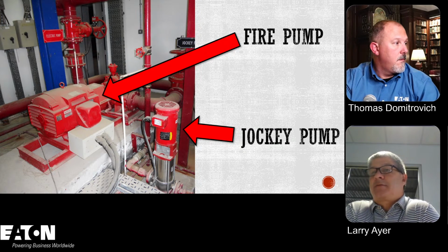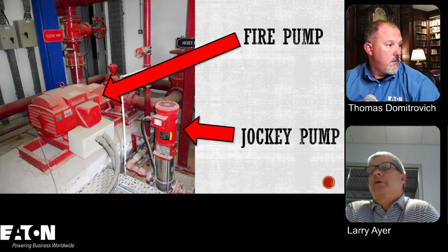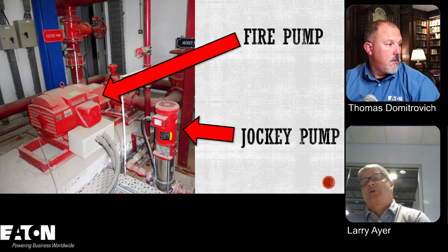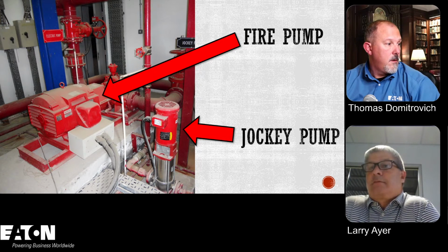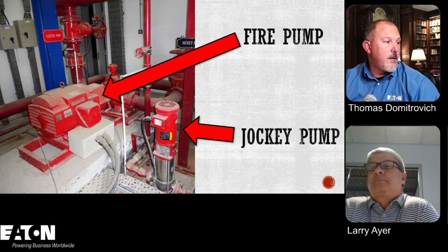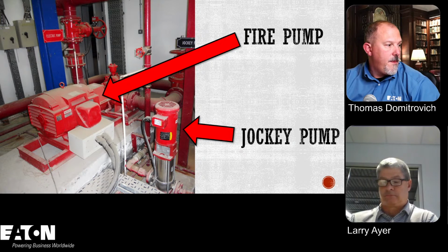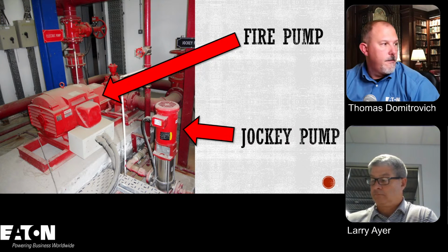I know that they have to be listed, and they have to be a little sturdier than your standard motor, so it can withstand some severe conditions when it's trying to operate. Yeah, so I'm looking. It says the standard for fire pump motors is UL 1000 and hold on. Added here, Standard 1004. So there is a specific standard for fire pump motors, and that is UL standard 1004.